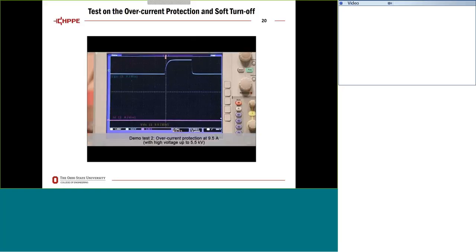The next test is at 5.5 kV, 9.5 amps. Again, the current goes up slowly, and eventually you will see the protection when the current reaches 9.5 amps. It also has a sharp shutdown at that time. So it's almost there.